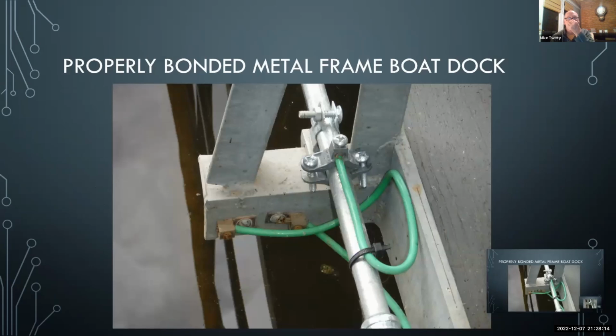This is a metal boat dock frame that's properly bonded. This green bonding jumper was required here. It goes back to the sub panel that's feeding this boat dock, and then it's jumpered here to the steel frame of the dock. The reason it's done is this is a metal conduit with seal tight on each end, so it's floating out here, it's isolated. So this had to be bonded to this metal dock in case it were to become energized. And the beam clamp that attaches the conduit to the steel is not a listed bonding connection, so this jumper had to be put on there.